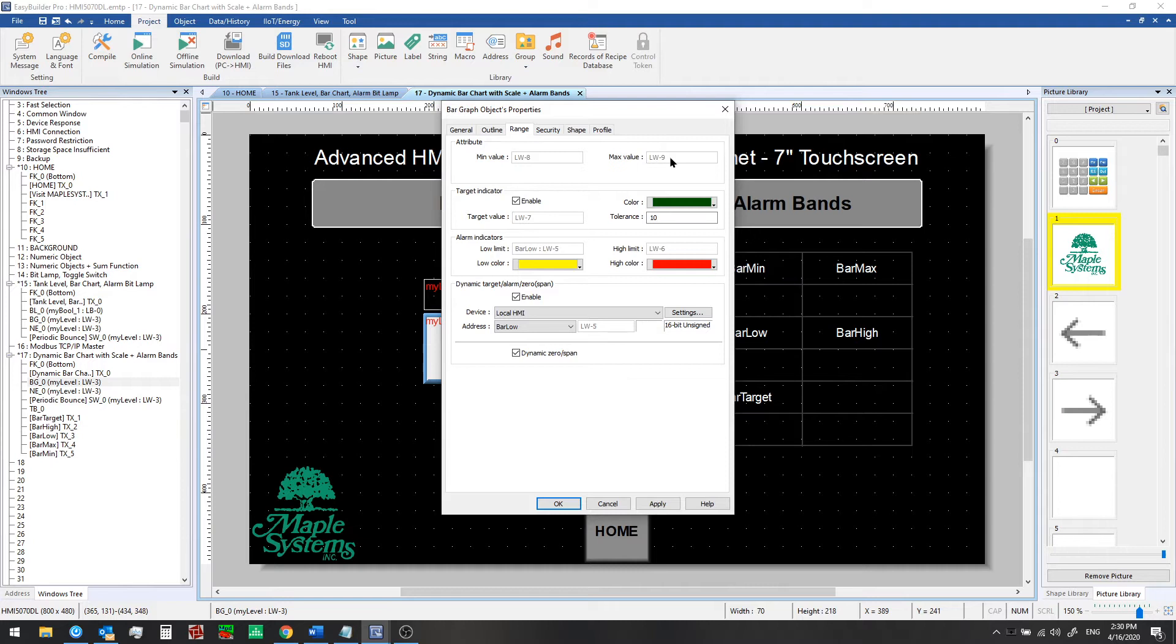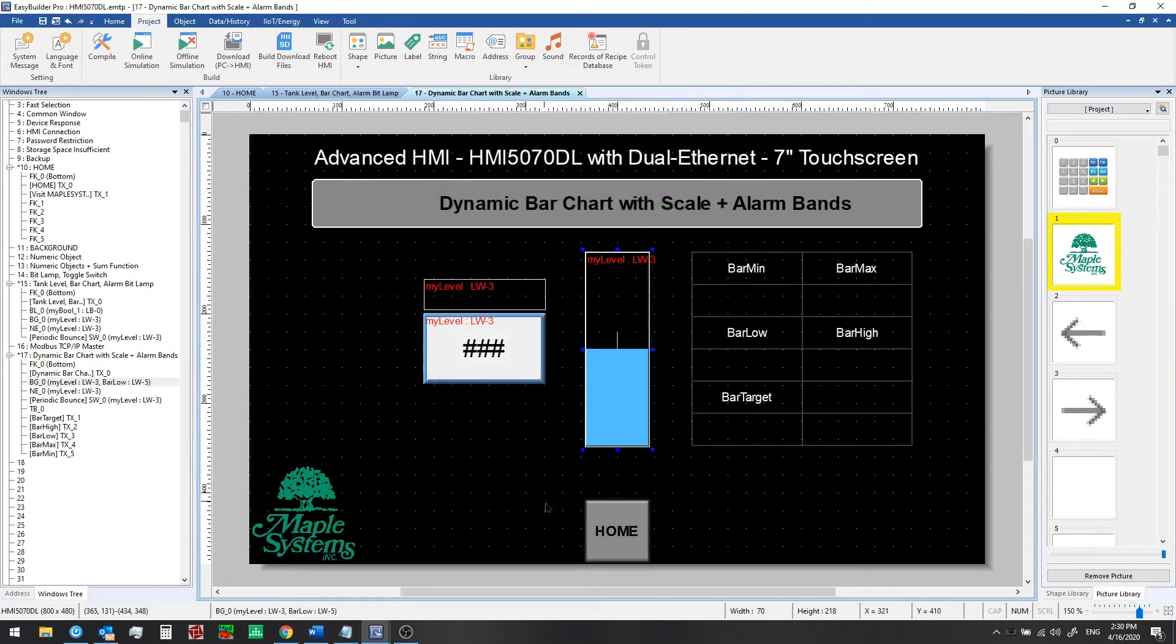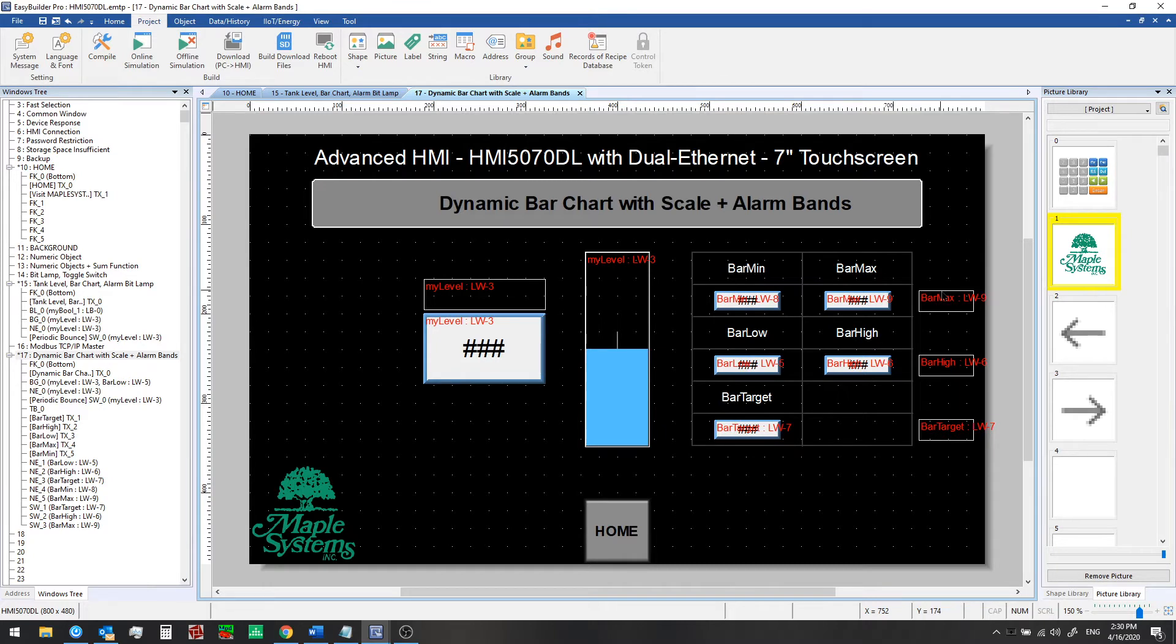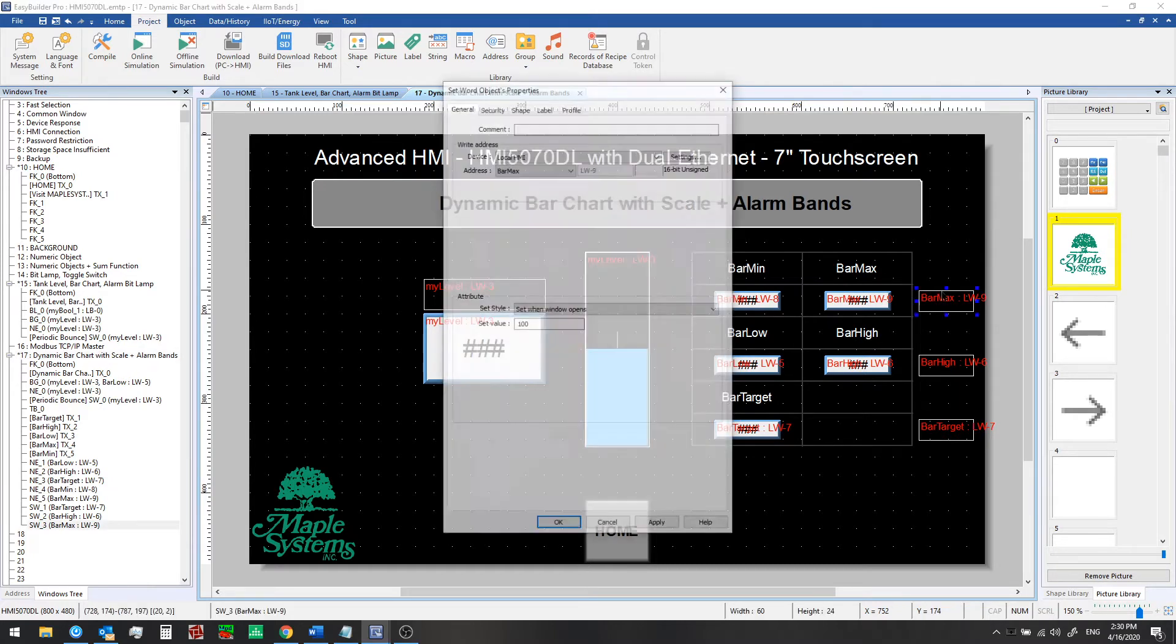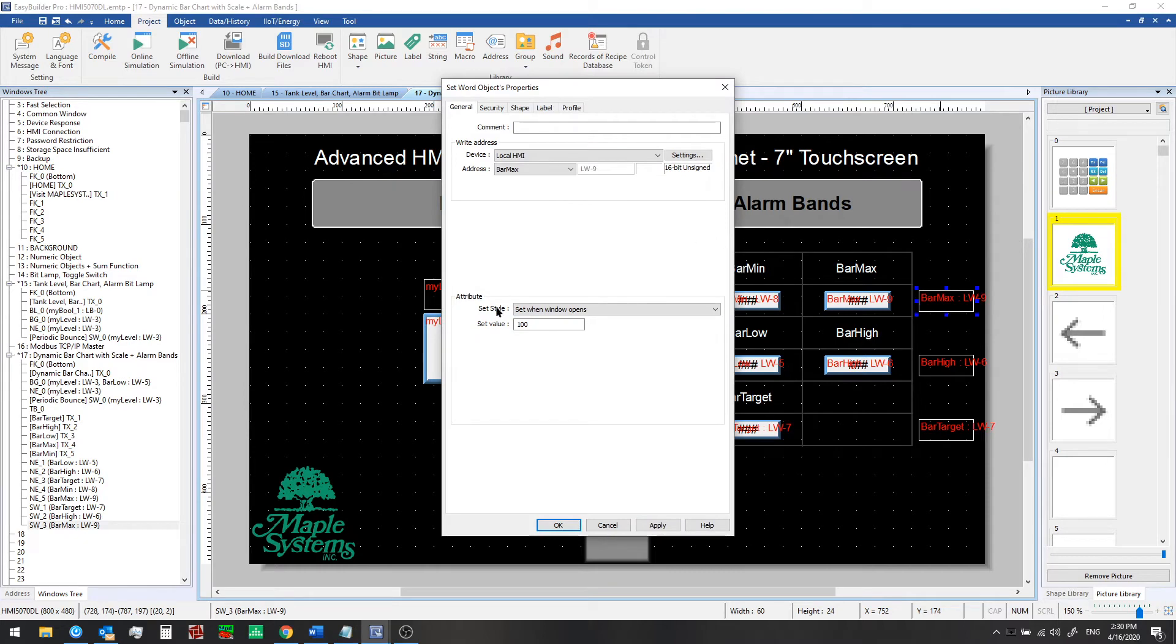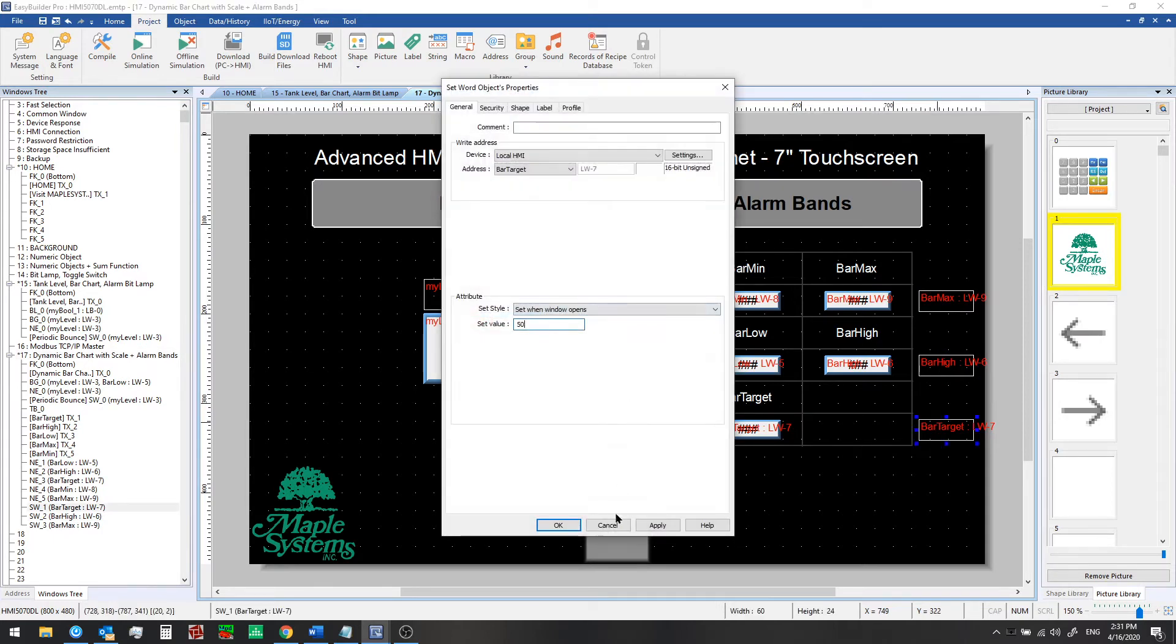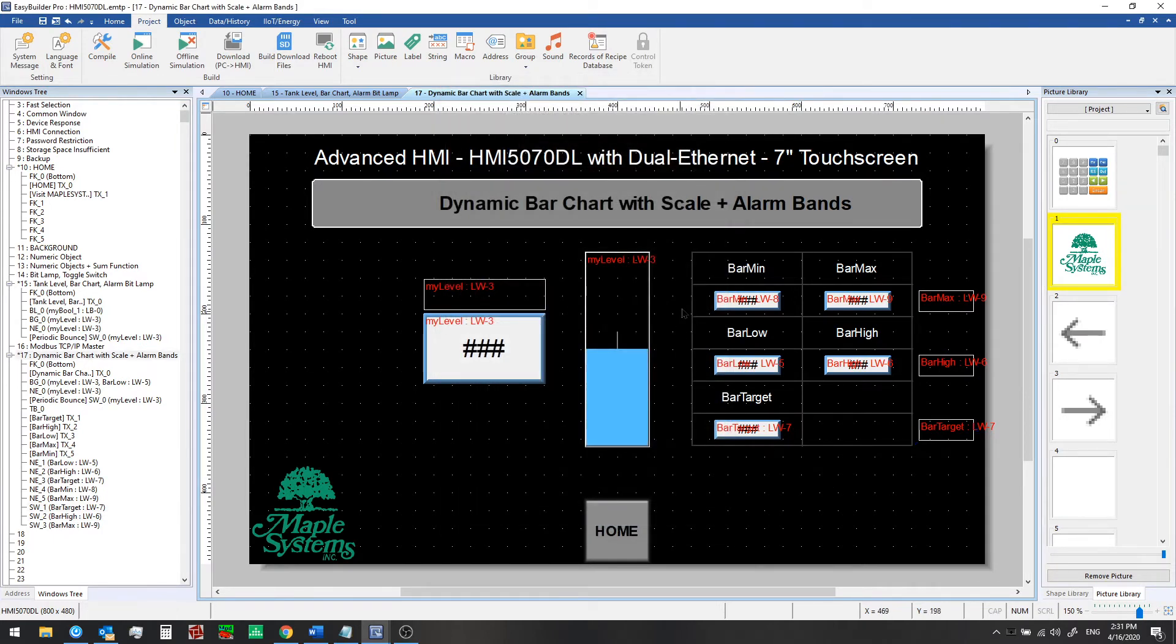Now that we've done that, we just need to add some numeric objects to the screen so we can input the values for these parameters. Okay, so now we've added our numeric input objects for each of these parameters for the bar graph. We also set up some set word objects on this screen so when we first open the window we'll start with some default values - for example, a maximum of 100 and a high alarm band value of 95 and a target value of 50 like we had before. But with the dynamic bar graph features that we've set up now, we'll still be able to adjust each of those parameters after we visit this window. Let's take a look.